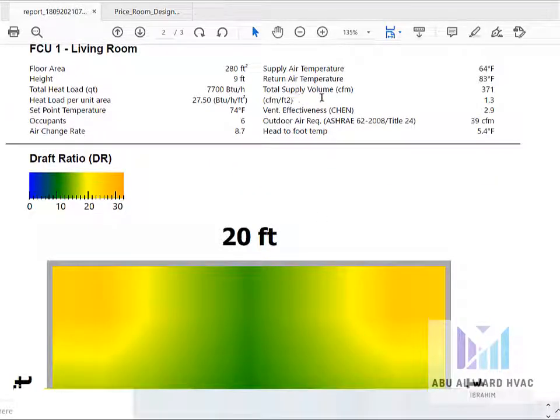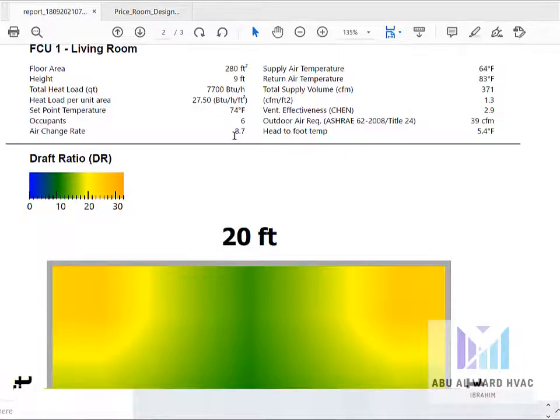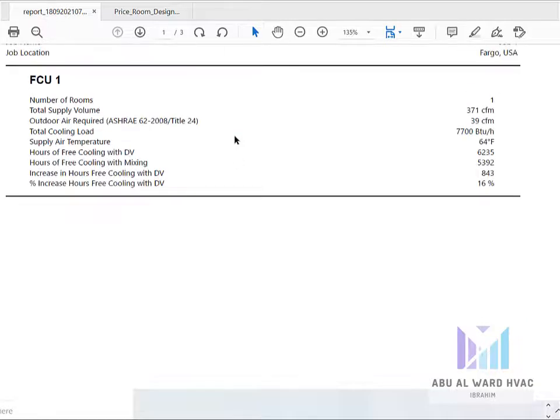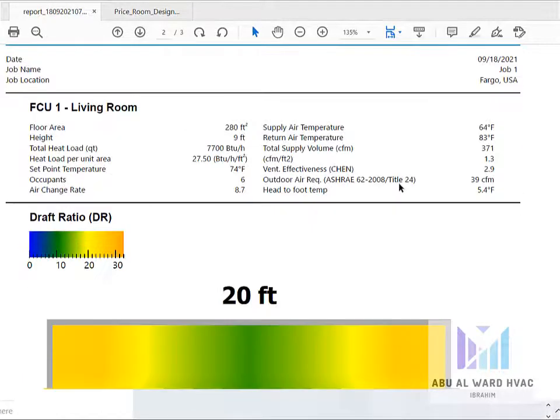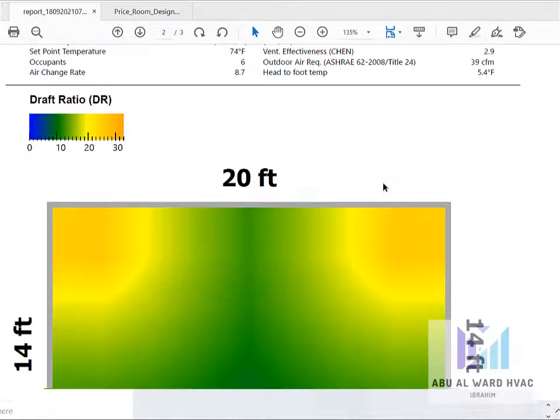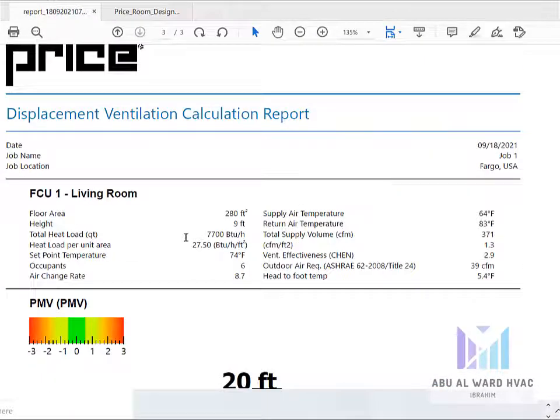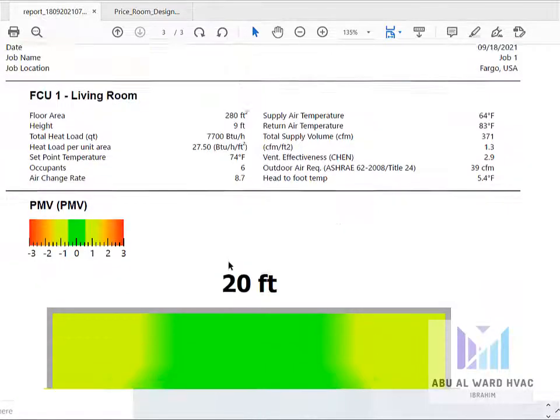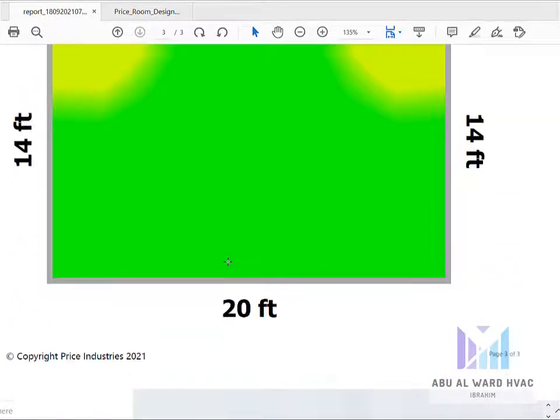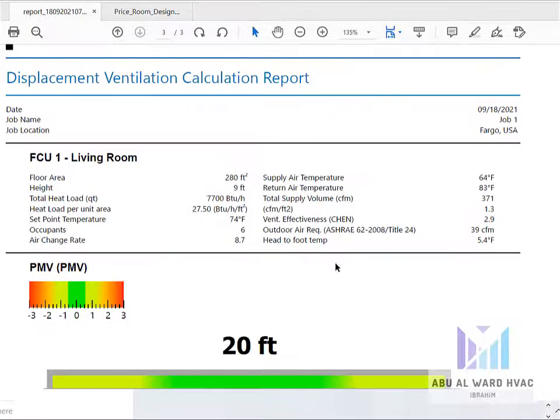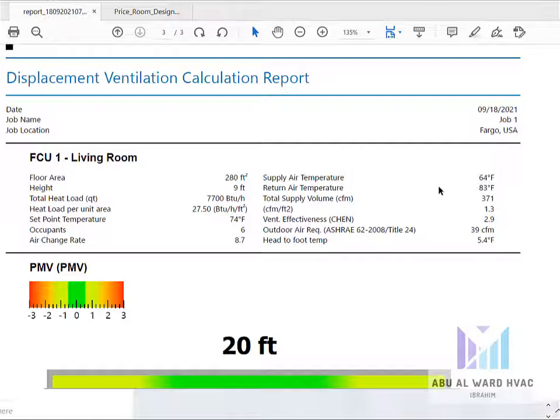This is the total supply volume 371 calculated by the software, and each grill is giving 185. It has two grills, each of them 185 CFM, but the total 371 and total load is 7700.